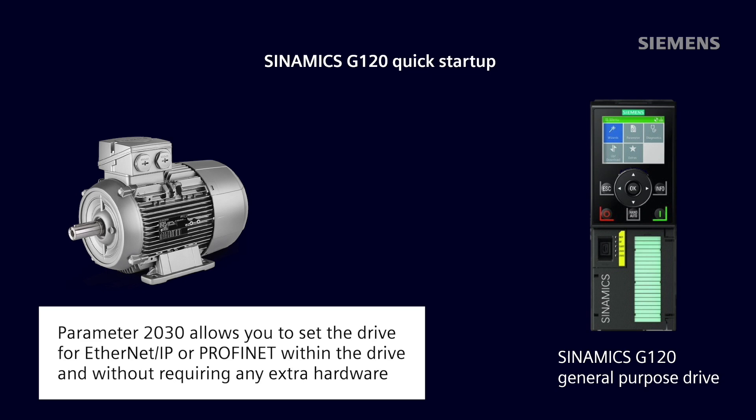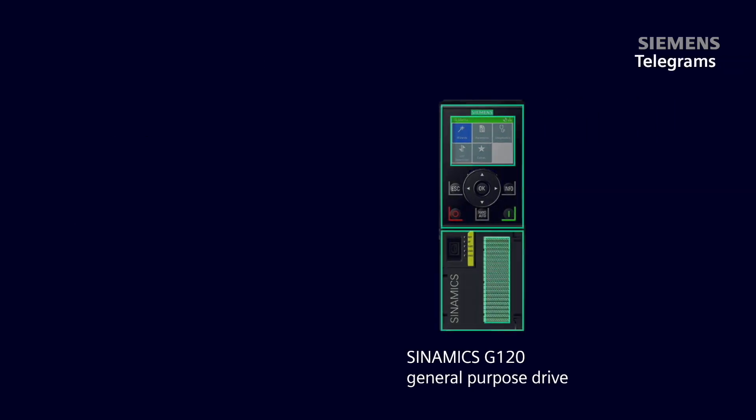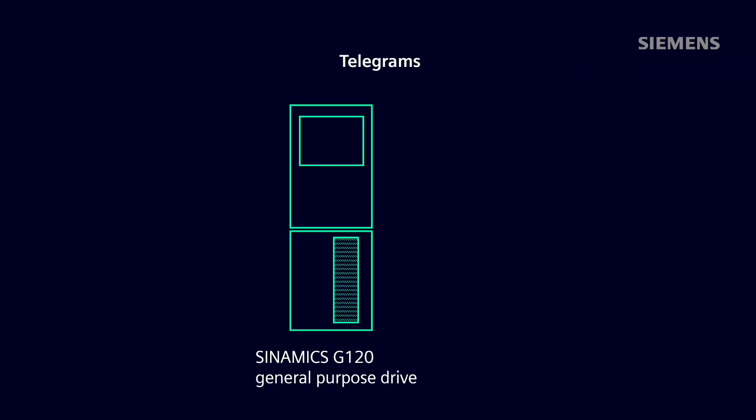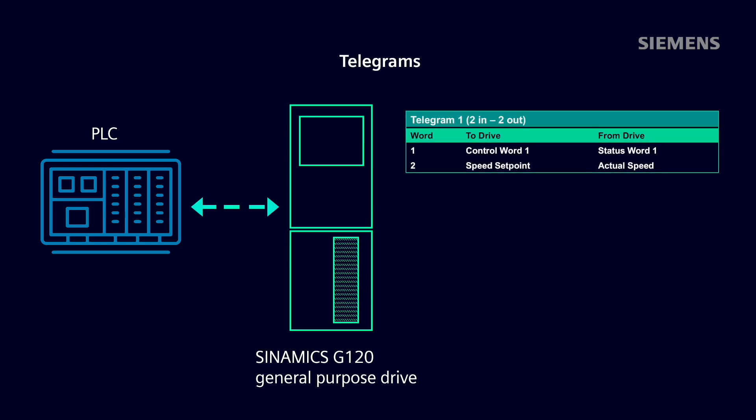You'll also need to select the telegram you wish to use. Telegrams are universal blocks of data that organize parameters and functions into a consistent format used to pass data between PLC and drive. Organized into 16-bit process words that contain relevant information, most telegrams have a control word, status word, speed setpoint, and speed feedback word in common. There are many different telegrams available, and there's even a free-form telegram that you can completely customize.